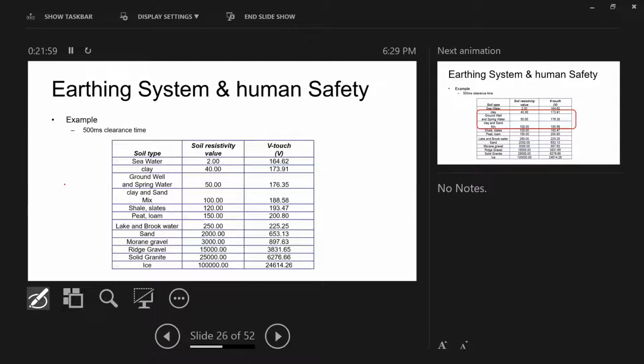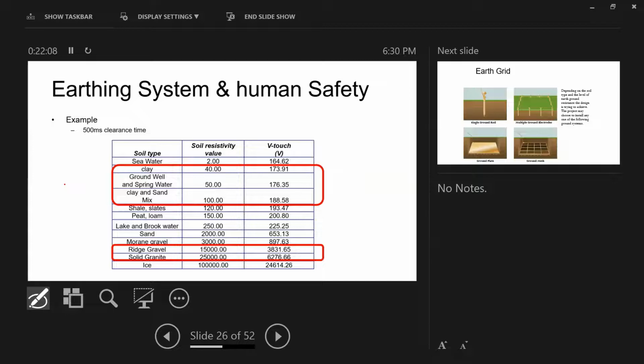Look, for example, if I have a 500 millisecond, half a second, clearance time, under different soil resistivity you have different allowable touch voltages. So if you have clay, the touch voltage is 173 volts under 500 millisecond clearance time. If you have solid granite or gravel, you can go to thousands of volts. That's why if you ever go to a substation or power station, they put gravel. They put gravel all over. Why? Because the soil resistivity of the gravel is very high. It will give you some sort of insulation.